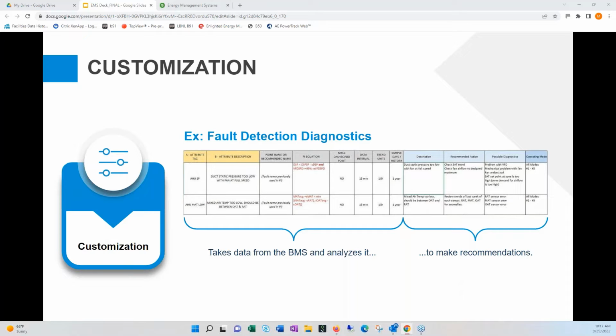It gives you three important things. One, the description, in this case the mixed air temperature low, which should be between the outside air and return air. It also gives a recommended action and a possible diagnosis.